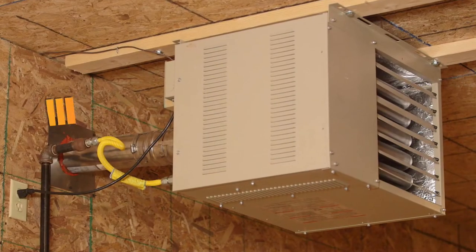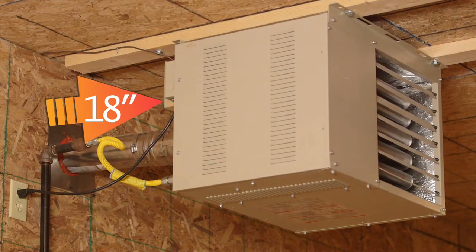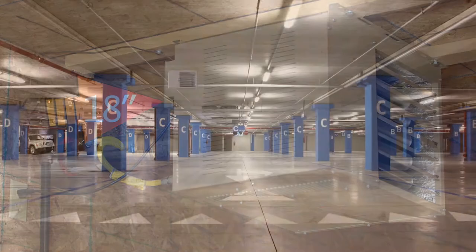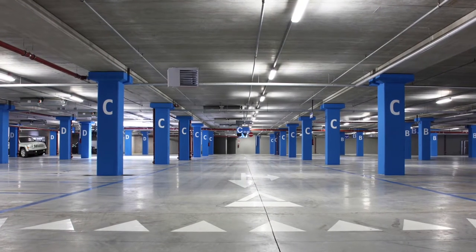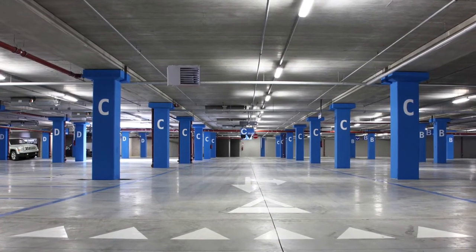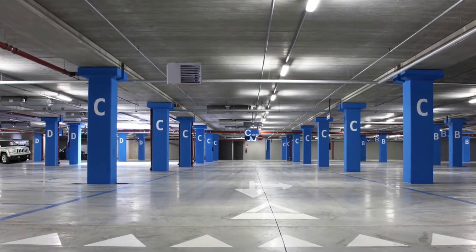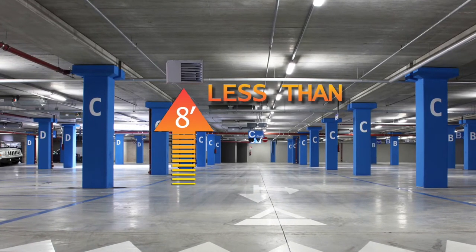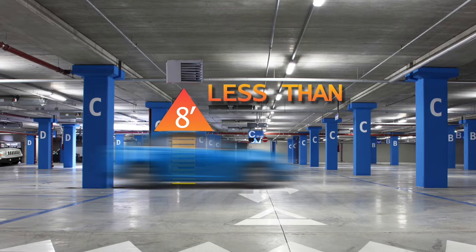You must also have at least 18 inches of rear clearance for gas, electrical, ducting, and fan access. For parking structures or hangars, you'll need permission from local building authorities for installations below 8 feet and a way to prevent damage from vehicles passing underneath.